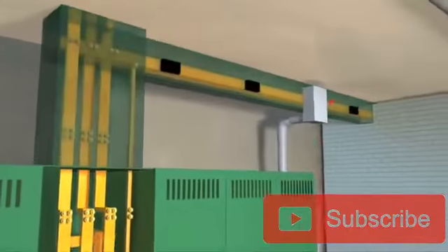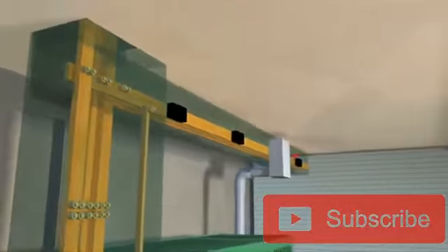Our draw-out breaker in section 2 is connected to bus duct. Bus duct is a rectangular or square metal enclosure containing bus bar. Its purpose is the same as electrical wire and conduit, but it is able to handle larger amp ratings. Bus duct is made up of 10-foot sections. Plugs or connectors are spaced every 2 or 3 feet for the purpose of attaching fused disconnect safety switches, which can then supply voltage to designated areas.